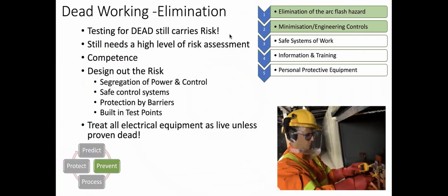I did mention dead working because this should be the first port of call for anybody who wants to reduce the arc flash risk. In this case, testing for dead still carries risk, I'm afraid. It needs a high level of risk assessment. For instance, the safety considerations for an individual making safe an underground high voltage cable are going to be of a much higher order than for somebody just isolating a piece of equipment at a local isolation point for themselves. So there has to be a high degree of knowledge and so on, i.e. competence.